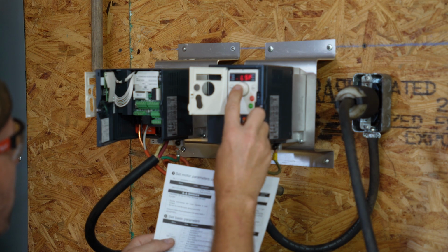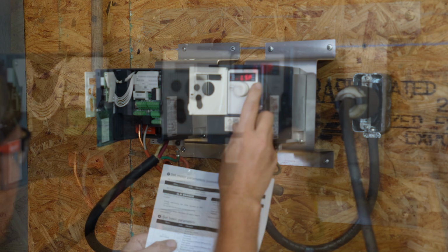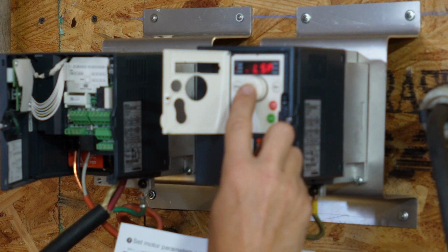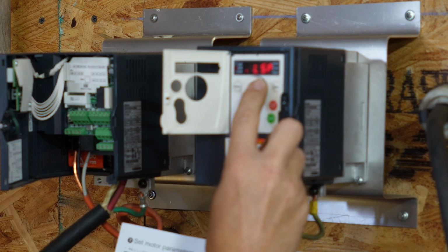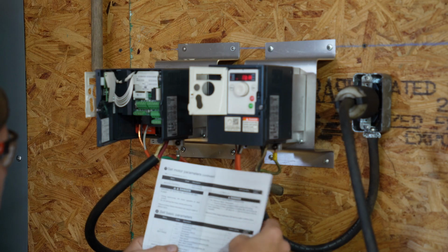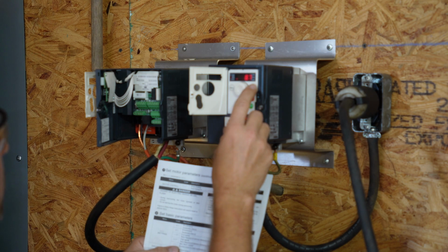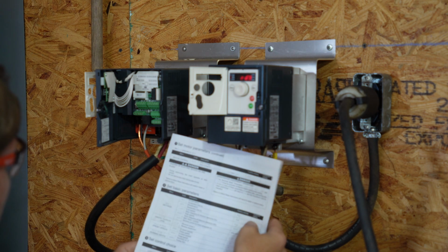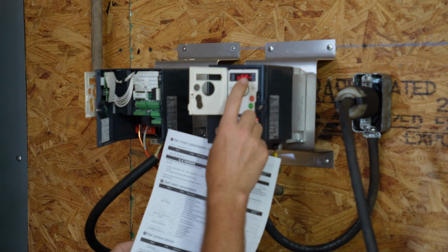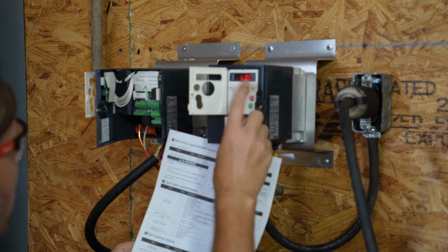Deceleration, same. LSP, motor frequency at minimum reference, 0. High reference is 60. Nominal current on motor nameplate, 8.7. Then we need to go to that IO setting. TCC is already on loc. Okay, that should do it.